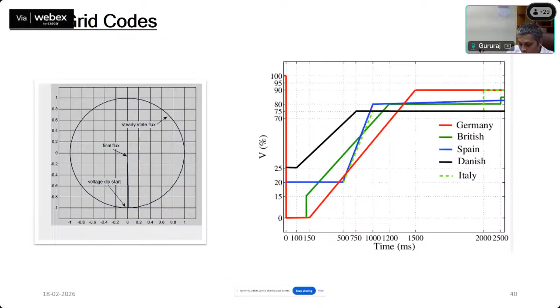But there's additional investment, and going for a full rated DVR is quite expensive, and in real time it may also consume some power during the steady state operation, which is not so efficient actually. And similarly, there is a concept of a D-STATCOM, distribution STATCOM, which is capable of injecting and absorbing reactive power. Bidirectional power support is possible. During the steady state operation also, they can be supportive in terms of maintaining the power factor, and during the transient and dynamic conditions, especially during the fault, could be balanced or unbalanced fault, D-STATCOM can be configured to take care of the requirement of the grid codes. But unfortunately, this will also add to the overall investment of the DFIG-based wind machine.